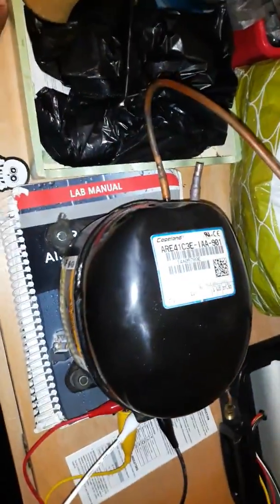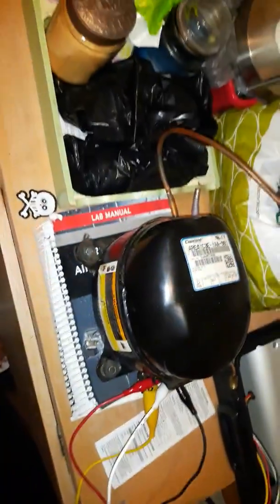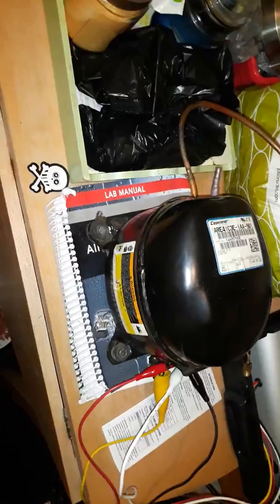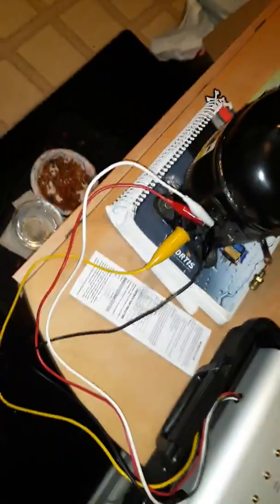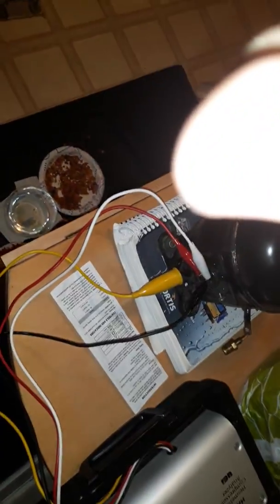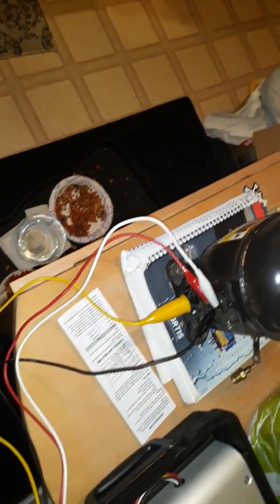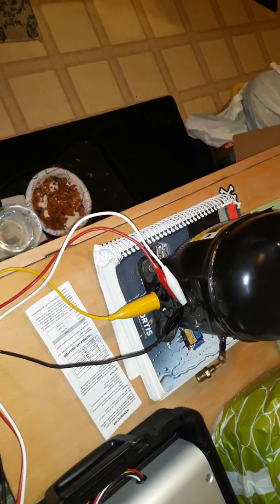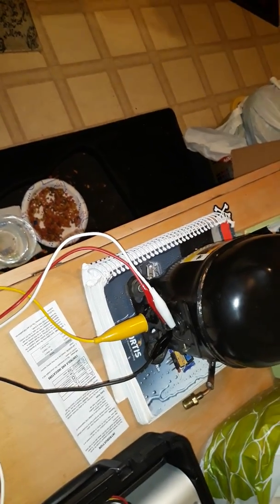It just would not start in the actual prep table, so we ended up changing it. Thought that maybe internally it was not working, but I ohmed it out. Everything seemed fine, all my readings. It wasn't shorted to ground.